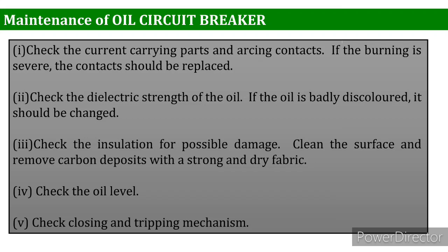The fifth one is to check the closing and tripping mechanism. The tripping and closing mechanism is the key. That's why the circuit breaker is installed. So if the closing and tripping mechanism is not working properly, like if there is a spring installed and the spring is loose, or if the bolt is not tightened, due to this problem the tripping and making or breaking process could be affected. So it must be checked while checking the oil circuit breaker.